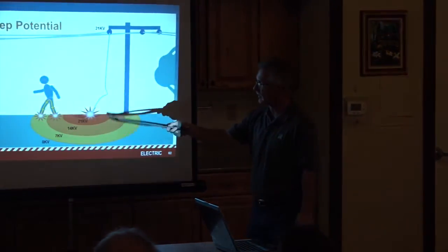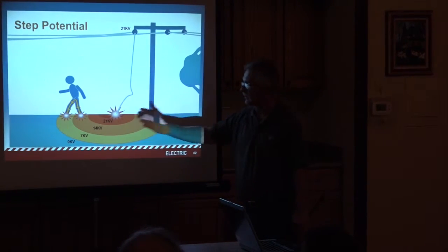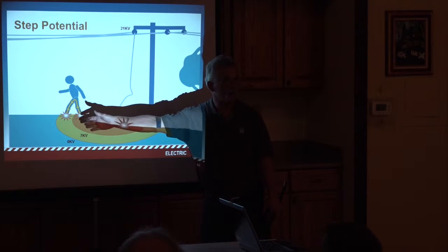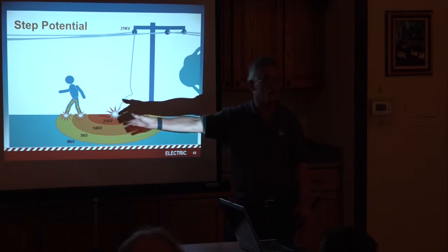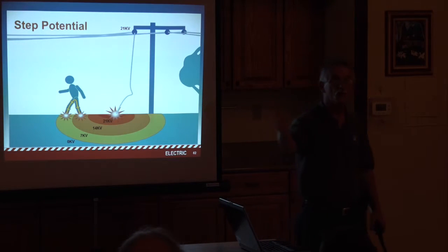So this is called step potential. Step potential means that when a wire touches the ground, the ground becomes energized. As you get further away from this wire, the energy starts to dissipate. It will dissipate down to 30 feet away. We talked about that being the safety margin. At 21,000 volts, at 30 feet, there's no more energy.